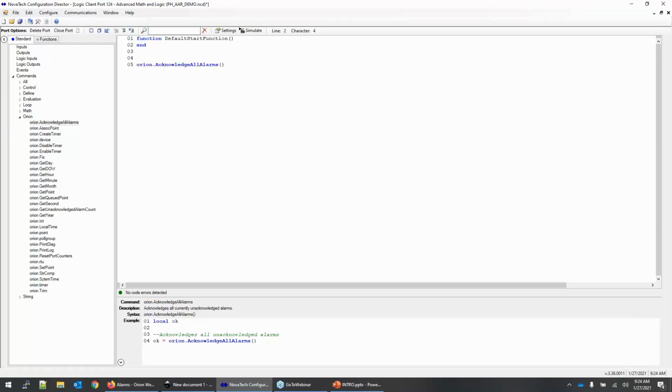Obviously, it's not in a function, so this isn't the actual application of it. You can utilize this code, and this will clear all of the alarms. We recently added a function in here so that if you put a value in here, as I just showed, this would now clear all the alarms just for zone 2 or that feeder 2. So you can use that to your advantage and tie those things together.